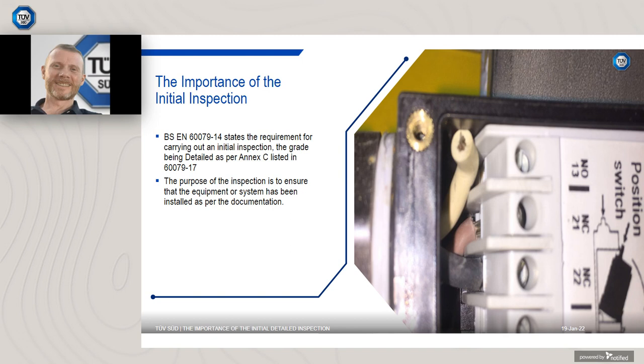The photograph shows a limit switch pickup on an initial inspection pre-factory acceptance test at a supplier facility. A spare core was cut and hidden in the housing. No crimps have been used. 60079-14 states multi-stranded cables shall be protected against separation of strands on termination. The repair required a new cable to be installed. This would have been costly and time-consuming had it been carried out at the project site.